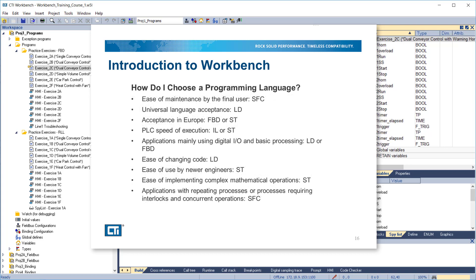How do I choose a programming language? For ease of maintenance by the final user, use sequential function chart. For universal language acceptance, use ladder diagram. For acceptance in Europe, use function block diagram or structured text. For speed of execution, use instruction list or structured text. For applications mainly using digital IO and basic processing, use ladder diagram or function block diagram. For ease of changing code, use ladder diagram. For ease of use by newer engineers, use structured text. For ease of implementing complex mathematical operations, use structured text.